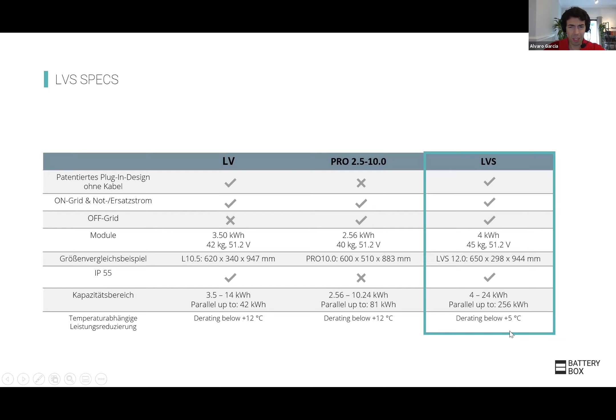So these batteries start from 4 kilowatt hours. That's a single module with 4 kilowatt hours. And by putting them in parallel, you can have up to 64 modules in parallel, allowing to have 256 kilowatt hours in a single system, as you can see here. And this unit derates also at 5 degrees.